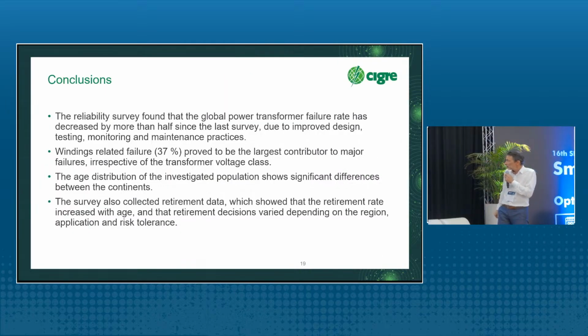So let's come to the conclusion. The transformer failure rate decreased compared to the last statistics 10 years ago. I didn't show you the second last statistic of 10 years before. That would have been too much. But the one result was that the failure rate is decreased during the last years. Winding-related failures are the biggest percentage in failure locations.